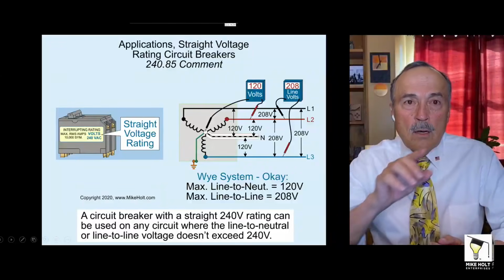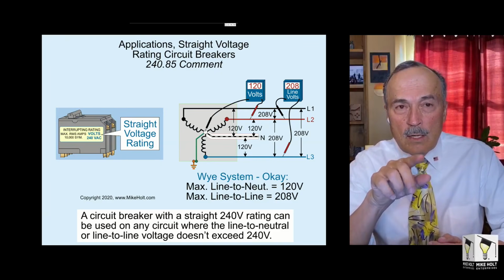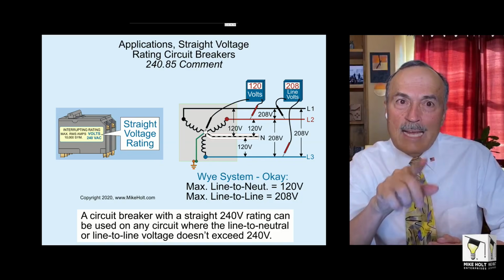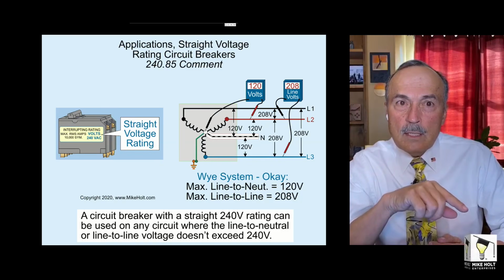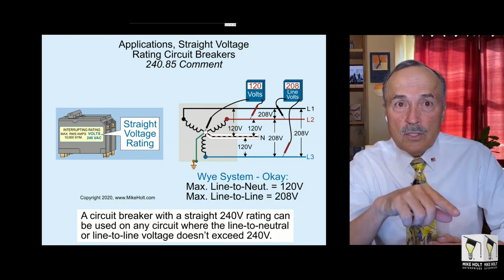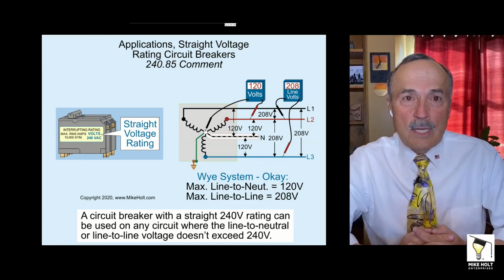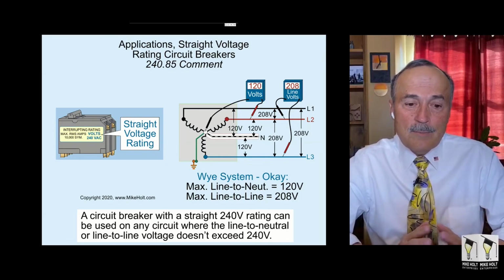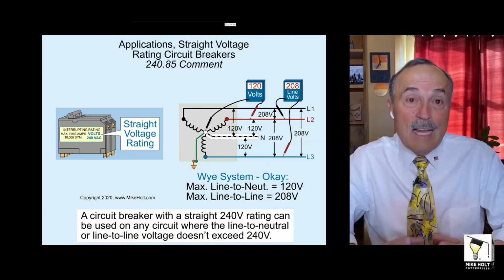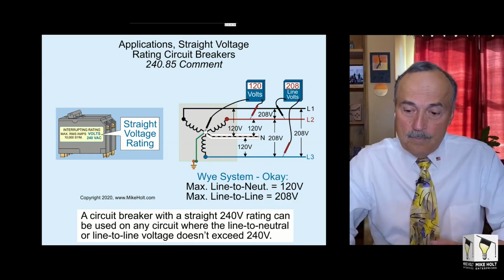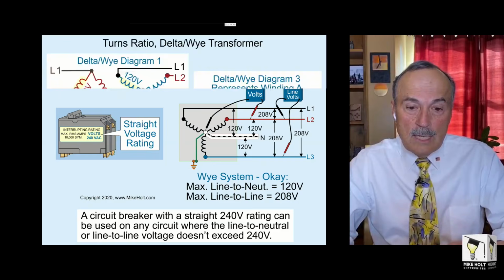Now, a straight rating on a breaker means that it really is a 240/240, which means that the maximum line-to-ground voltage is 240 and the maximum phase-to-phase voltage is 240. Well, we're not going to be using a straight rated breaker because they're not that common, they're not necessary, and they cost more money for single phase anyhow.